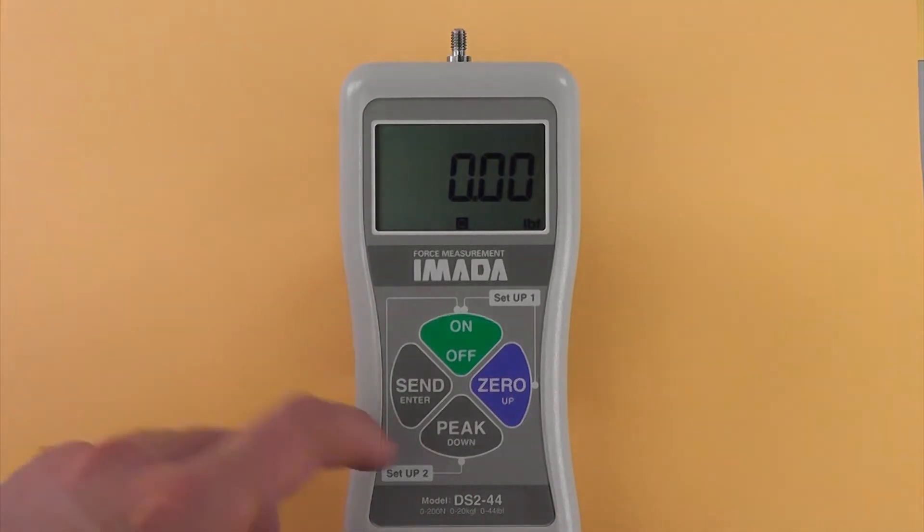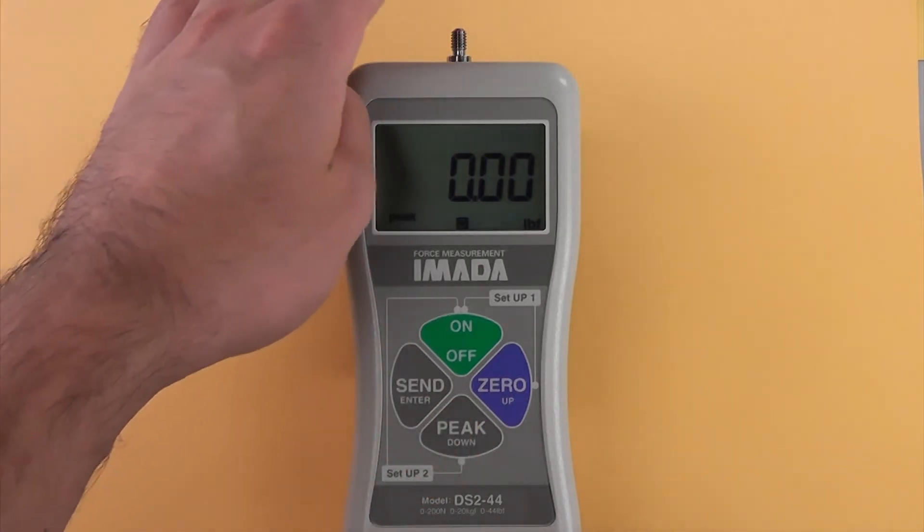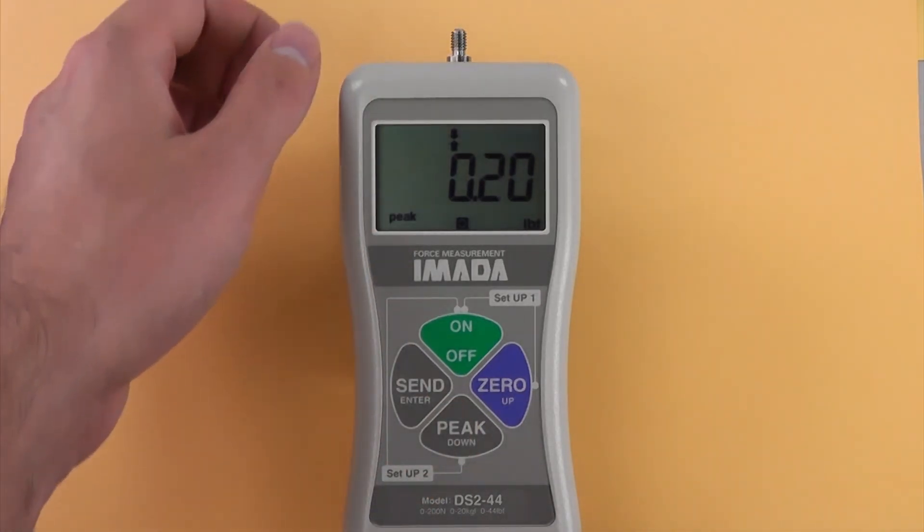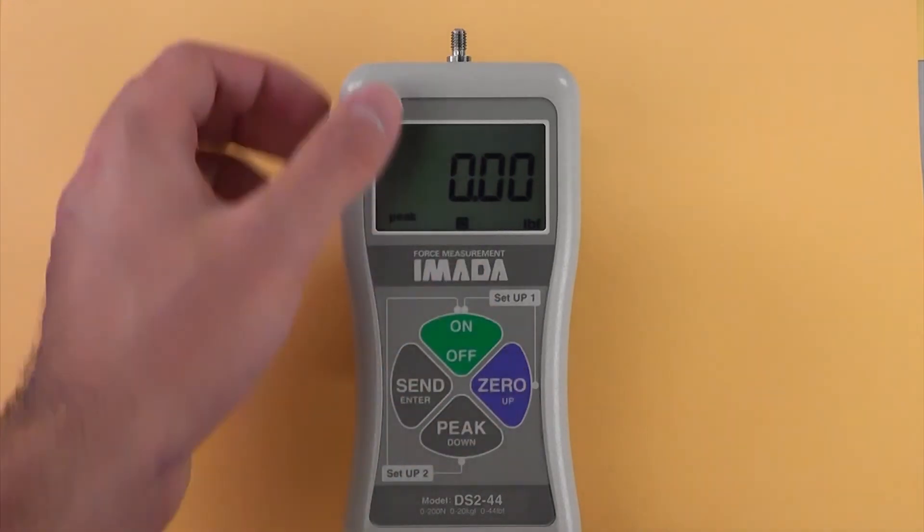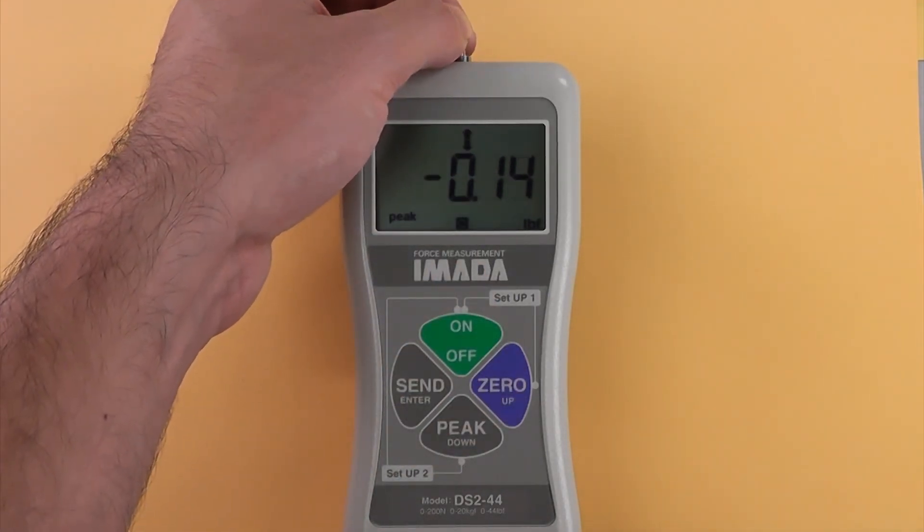For peak measurement, press PEAK. Notice that PEAK appears on the display. Peak values will not change until a higher value is measured.